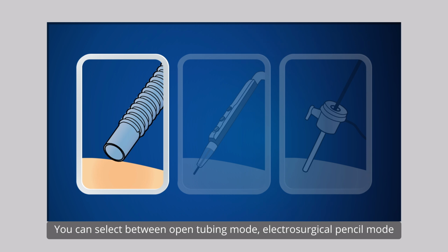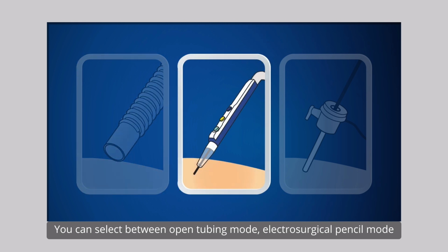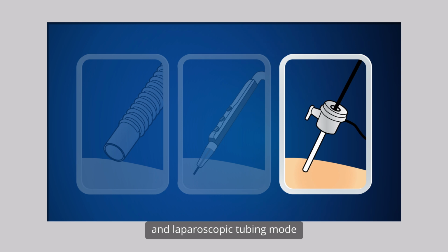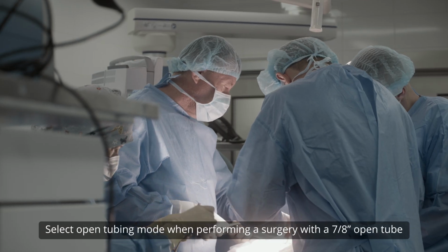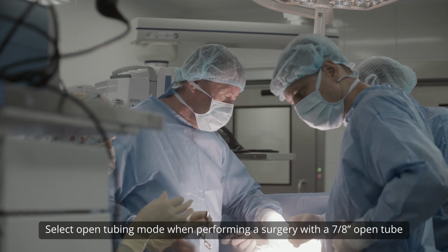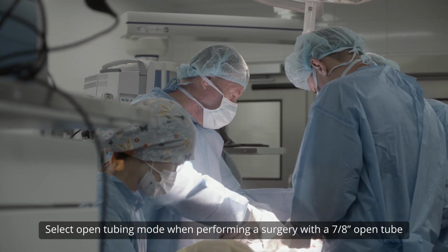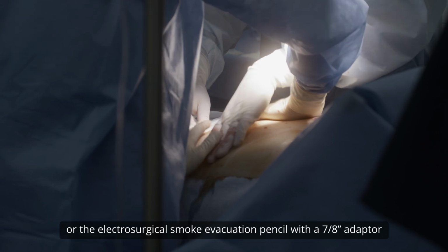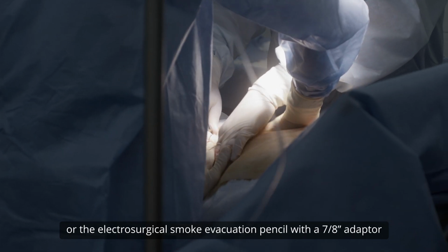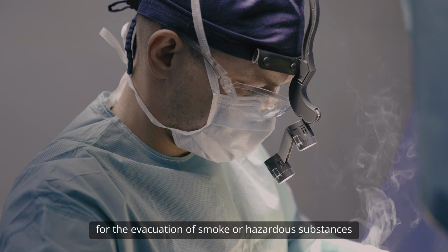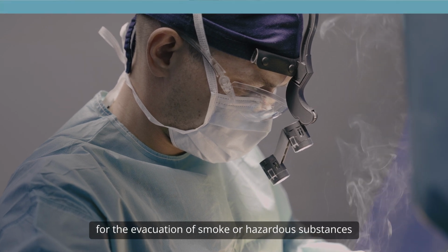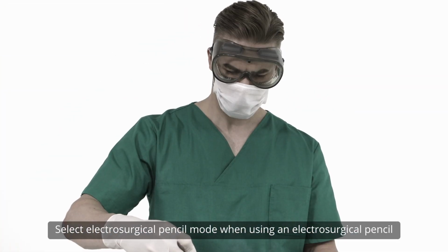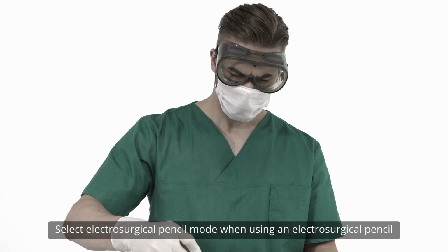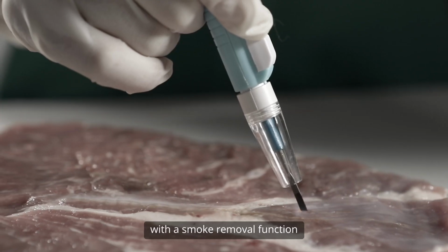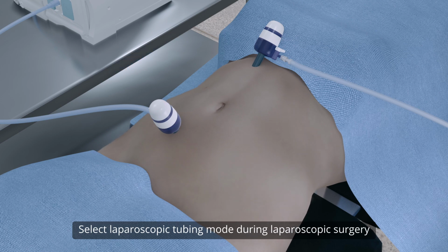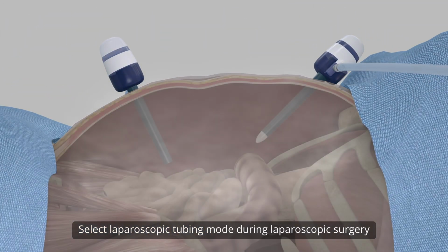You can select between open tubing mode, electrosurgical pencil mode, and laparoscopic tubing mode. Select open tubing mode when performing a surgery with a 7/8 inches open tube or the electrosurgical smoke evacuation pencil with the 7/8 inches adapter for the evacuation of smoke or hazardous substances. Select electrosurgical pencil mode when using an electrosurgical pencil with the smoke removal function. Select laparoscopic tubing mode during laparoscopic surgery.